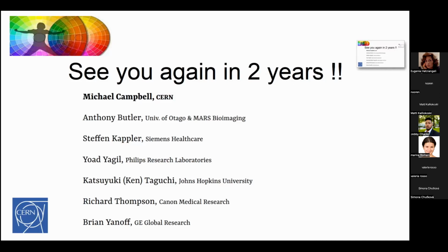But in fact, with photon counting, because you can go much lower power if you want to, you can produce cheap machines, air-cooled, lower dose. So one of the big savings, I was talking about it with Raj from MGH, is that when they put in a new CT scanner, they spend as much on refitting the room as they do on the scanner, which is, you know, $1 million to refit in Boston. Whereas the scanner we've got in Christchurch, because it's low X-ray power, we put it in the office of the radiographer. We could train the radiographer in 4 hours because all they need to do is put the start and end position. You don't need all these fancy things about what power or what energy you're using. You just do the whole lot. It's just an anatomical thing.